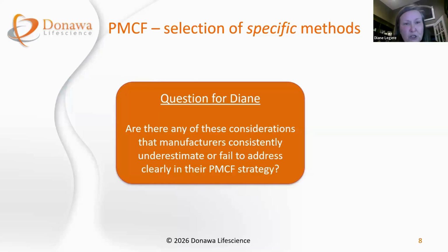Or that there isn't anything specific with comorbidities that are affecting the benefit-risk. So I really want to just see an easy transition from your clinical assessment, your risk, over to your PMCF. Even if we know all the known risks and we're going to continuously assess this, it should be easy. I shouldn't have to be shaking my head, reading it again and trying to make that trace.